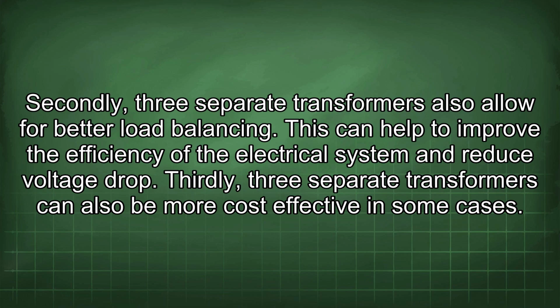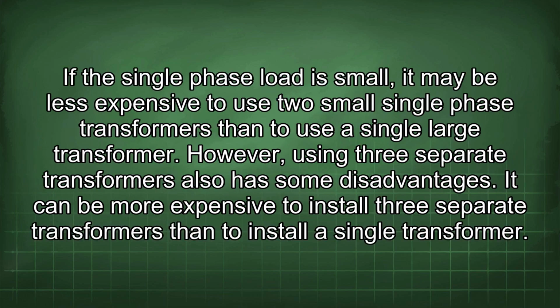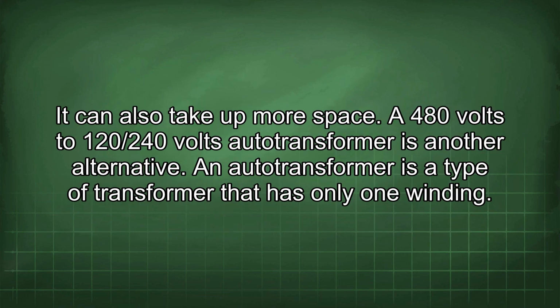Thirdly, 3 separate transformers can also be more cost-effective in some cases. If the single-phase load is small, it may be less expensive to use 2 small single-phase transformers than to use a single large transformer. However, using 3 separate transformers also has some disadvantages. It can be more expensive to install 3 separate transformers than to install a single transformer. It can also take up more space.